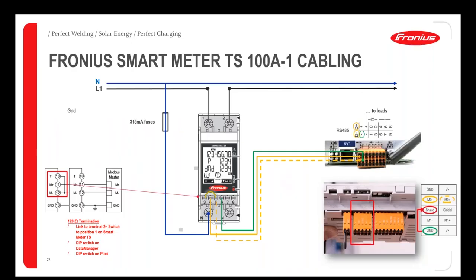So let's have a look at the installation for the meter. Very simply, we connect the supply phase cable, the live cable, into terminal 1 and then out to the loads from terminal 2. The neutral connection goes down into the terminal on the bottom of the device here, and we have our data connection here. We have a three core cable going to our data manager. We need data plus, data minus, and ground.